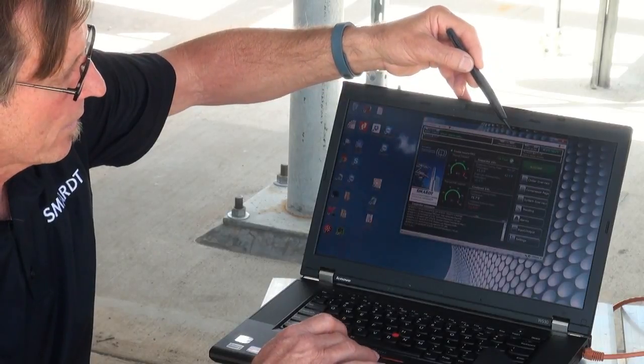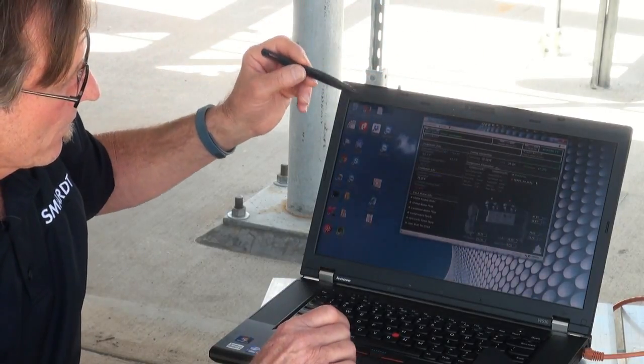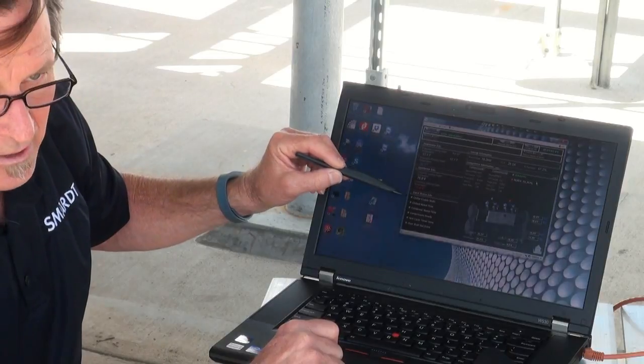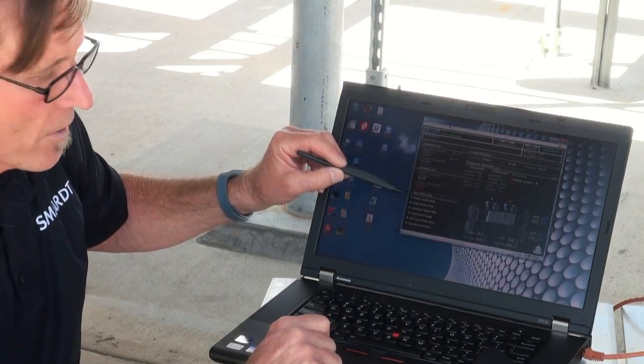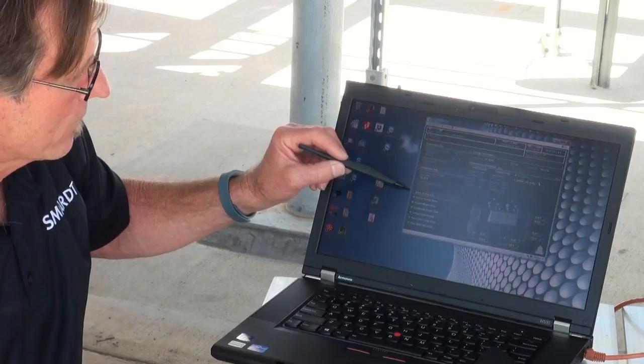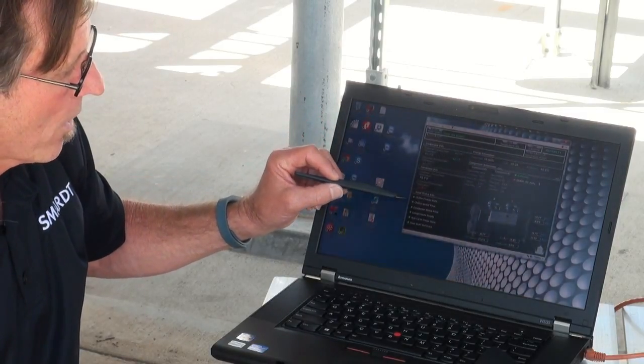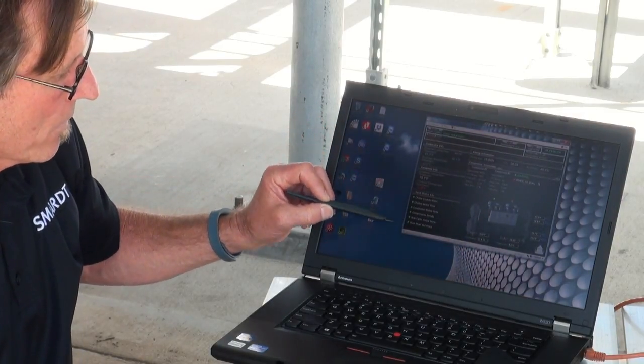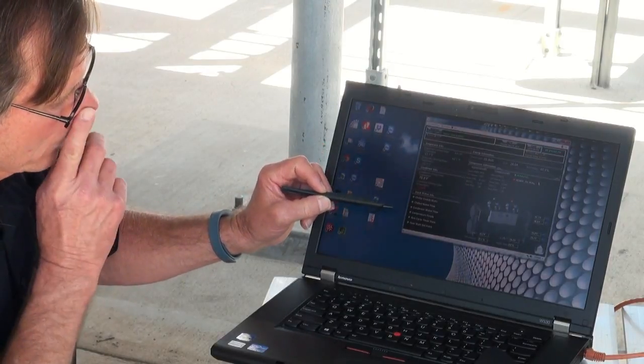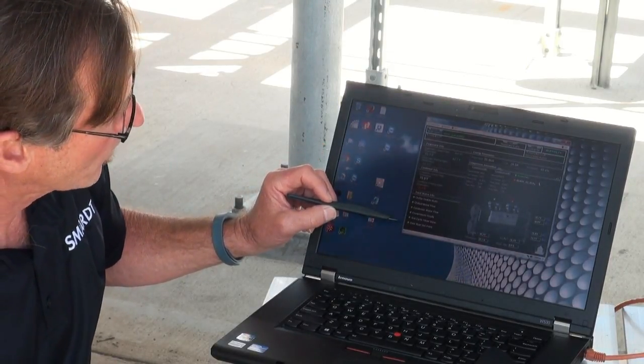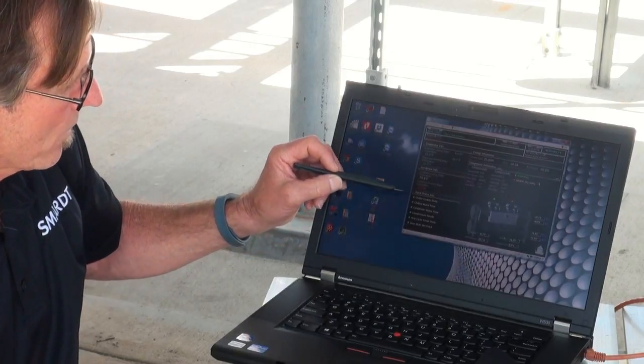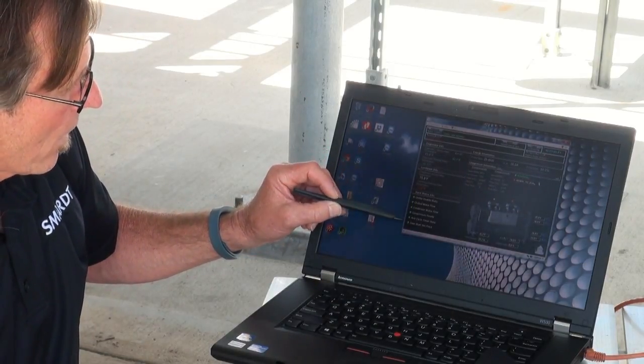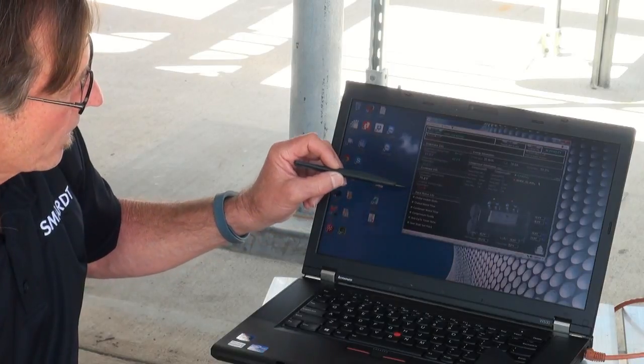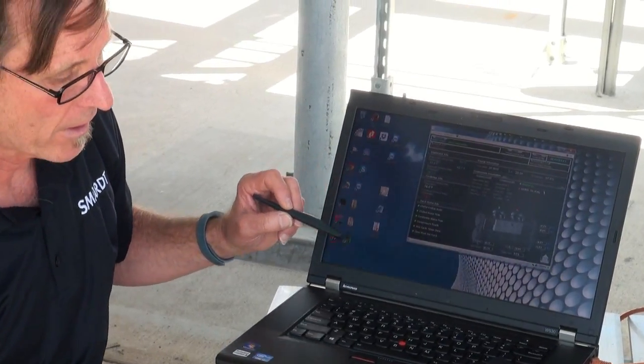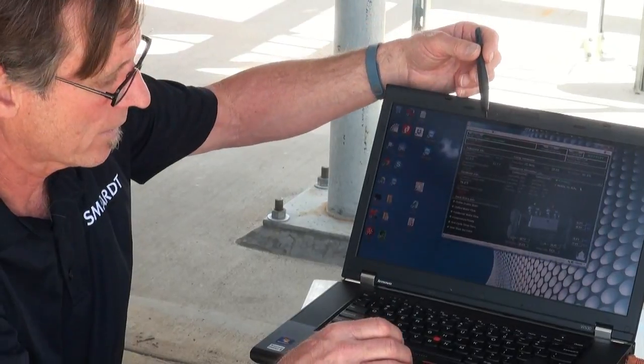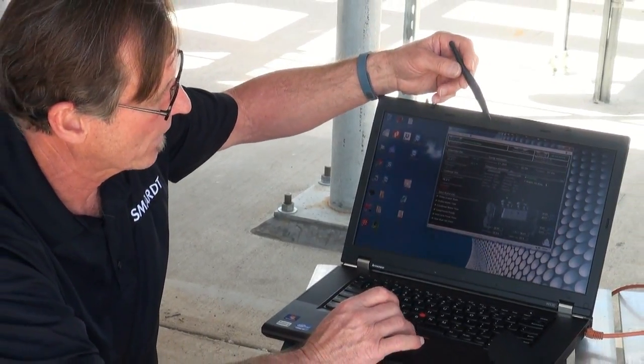As soon as you do that, this chiller enable state will turn green, and that part of the starting sequence is satisfied, and you'll be ready to go. As long as you have chill water flow and condenser water flow, as long as all of these are green, it'll take off and run. See, right now we'll probably stage on another compressor soon. We're over our set point, so that's a good indication for you guys. So if you're wondering why your chiller's not running, that's a good place to go to get a clue.